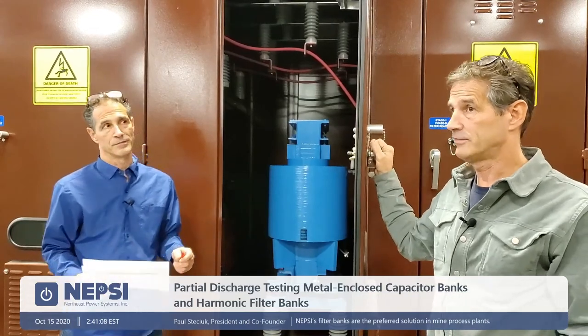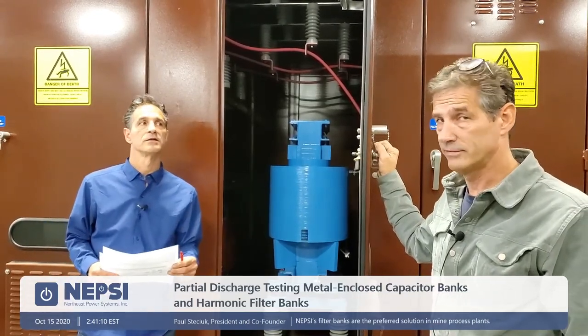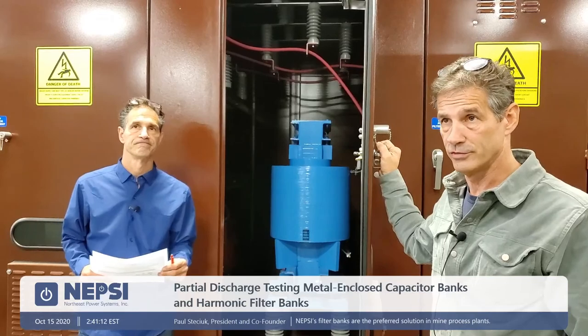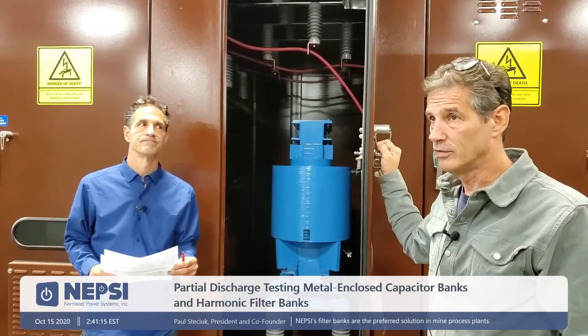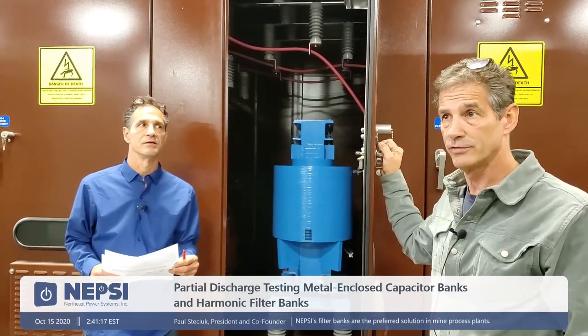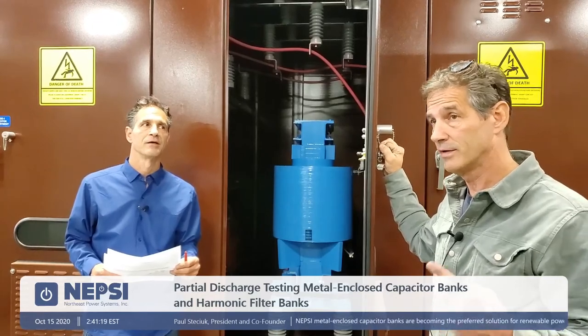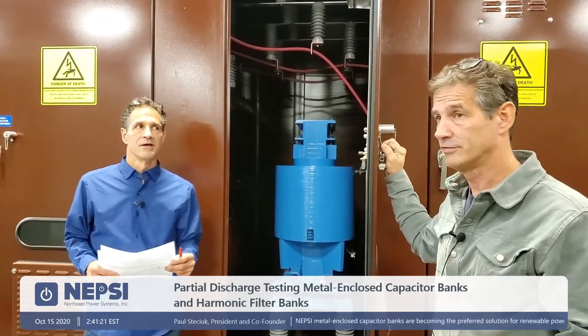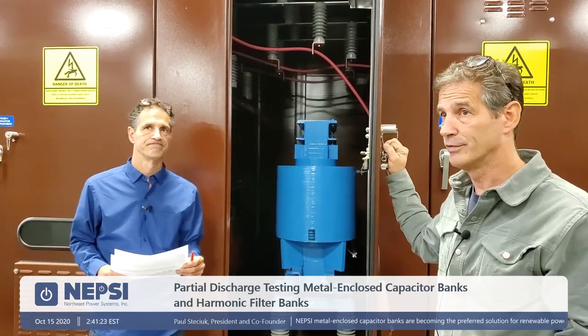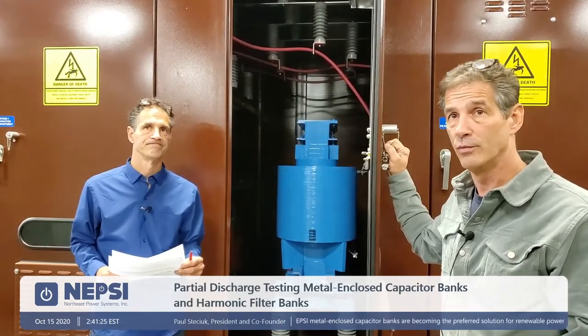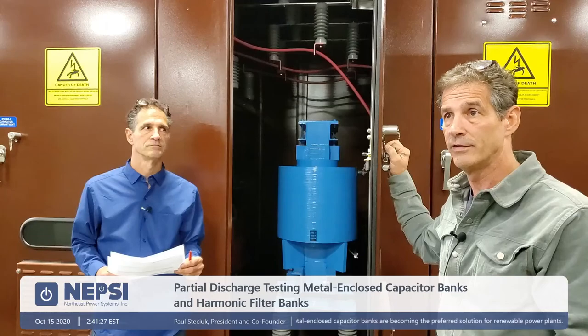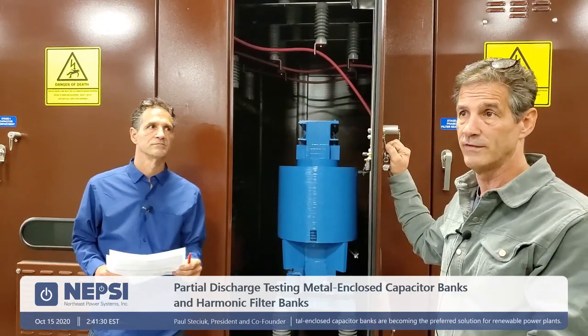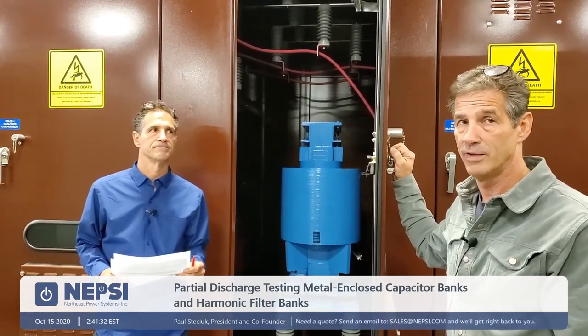Yeah, so in that test, we had impulse first, we passed the impulse, and then when we did the partial discharge test, that was the only one we were failing. We did not fail for high pot, did not fail for impulse. Partial discharge was just on the edge, failing for some reason. We went searching around the equipment and found the lifting bracket that's used to lift the breaker and put it into place had been left on.